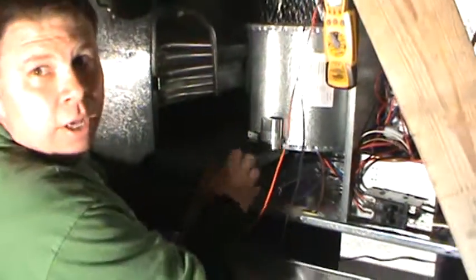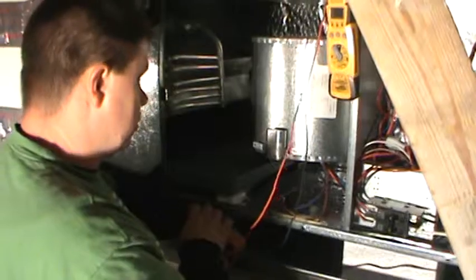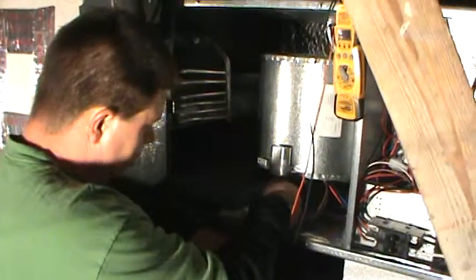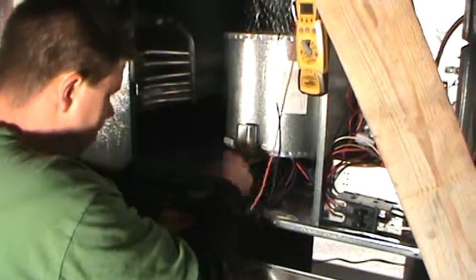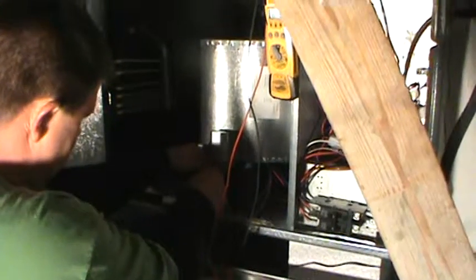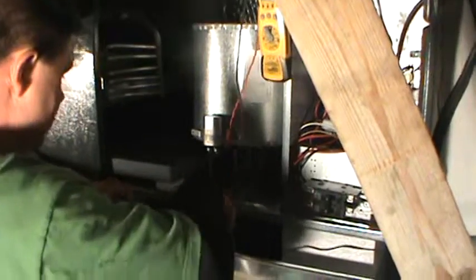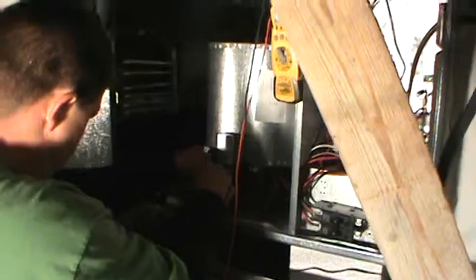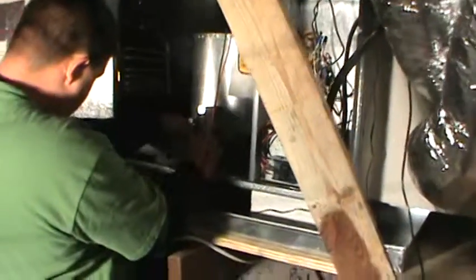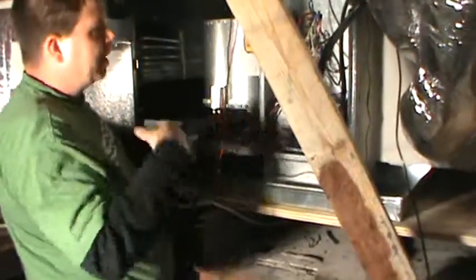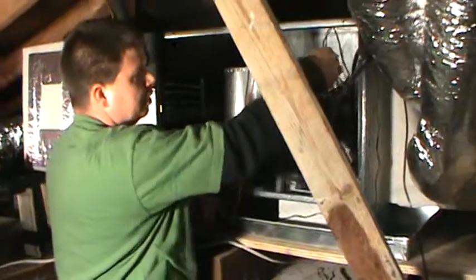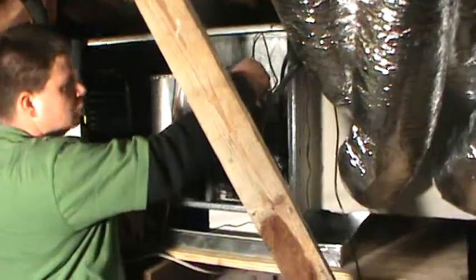But if not, then you should let the customer know, look, it's working now, but it is low, and it could go out on you soon. That capacitor's good. Hook your wires back up. At this point, we got the power off. You want to go ahead and check all your wire connections.